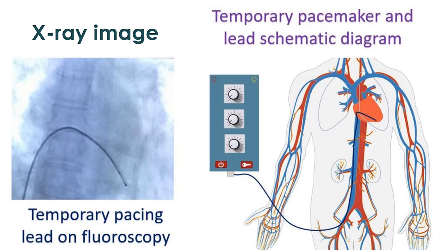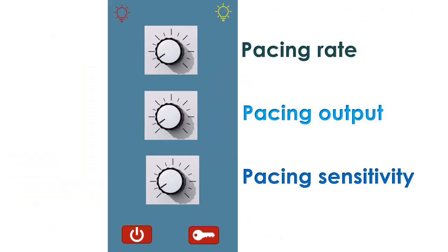The diagram shows the temporary pacemaker and lead reaching the right ventricle, the right lower chamber. The X-ray fluoroscopy image shows the temporary pacing lead tip in the right ventricle. A temporary pacemaker usually has three controls to change the pacing rate, pacing electrical output, and sensing sensitivity.